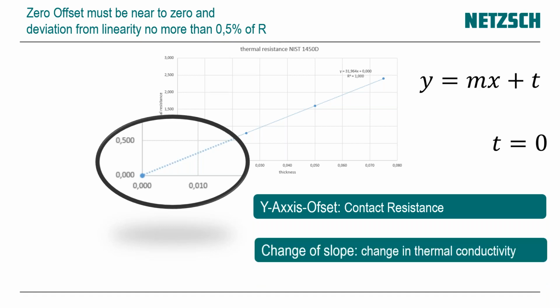And the change of slope is a change in thermal conductivity. So that means from this linearity check, where you measure different thicknesses of the same material to check if your instrument is working linear for that material in that thickness range, lambda can be calculated from 1 divided by slope without the influence of contact resistance. And a proper measurement should deliver no contact resistance. That means T is 0.